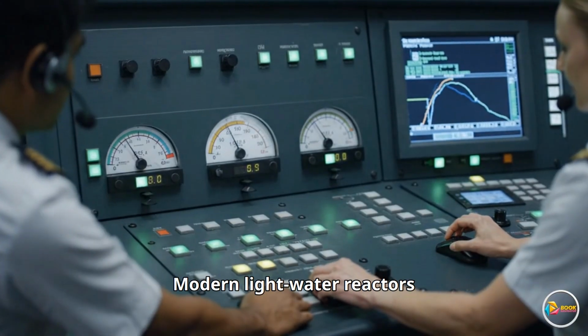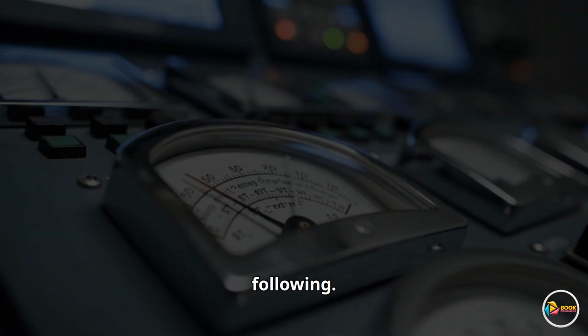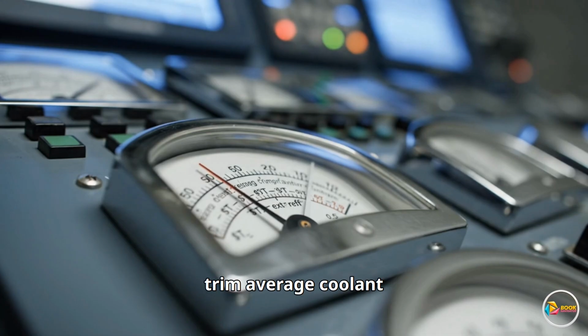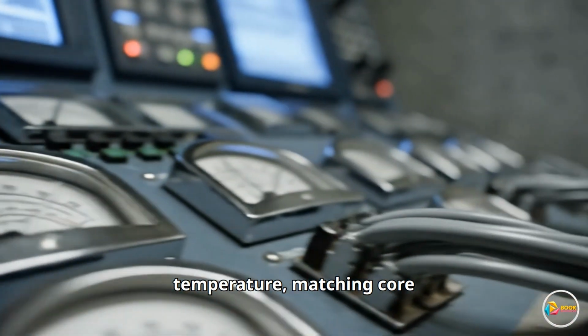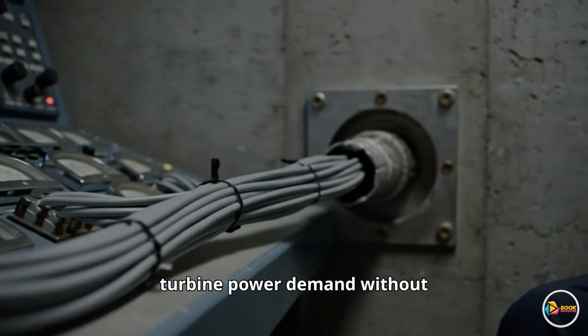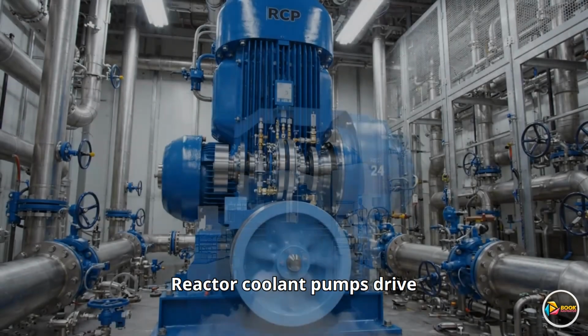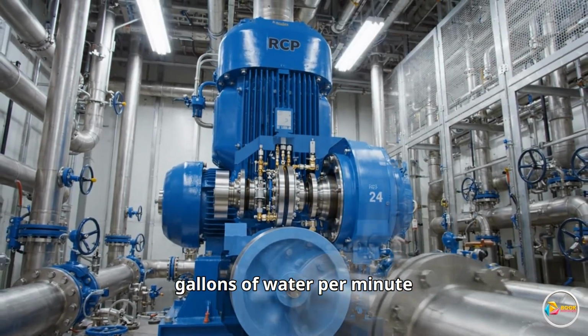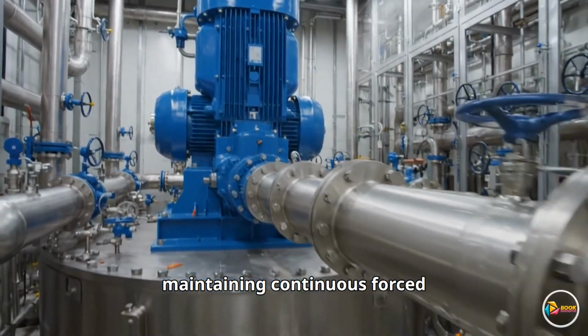Modern light water reactors can perform flexible load following. Automated control systems continuously trim average coolant temperature, matching core heat generation to steam turbine power demand without operator intervention. Giant reactor coolant pumps drive hundreds of thousands of gallons of water per minute through the core, maintaining continuous forced convection across every fuel assembly.